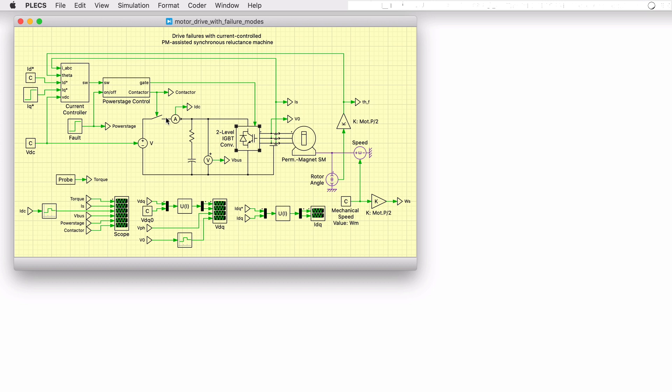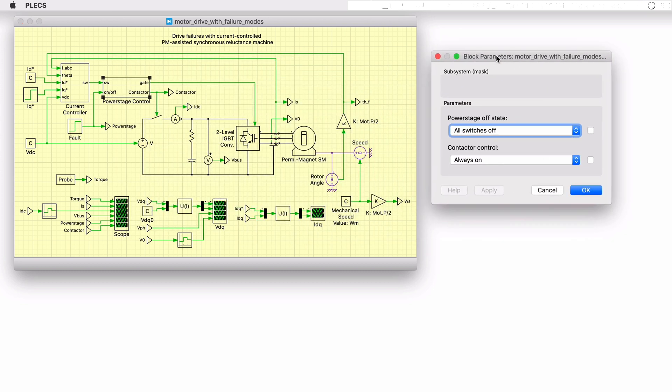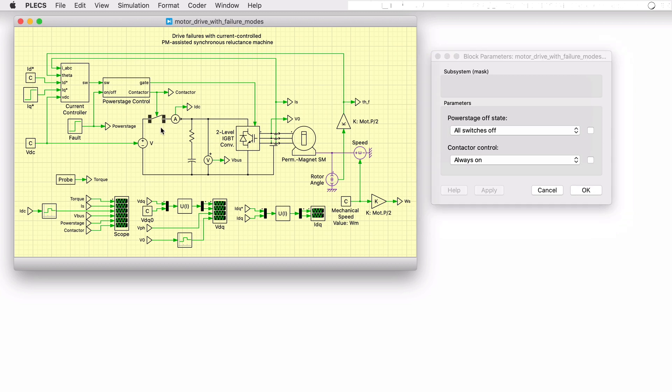The power stage control subsystem can be configured to mitigate this fault condition with two different strategies. One fault mitigation strategy is to open the battery contactor when a power failure is detected. Opening the battery contactor would result in charging up the DC link capacitor until the bus voltage is equal to the rectified back EMF of the PM machine.